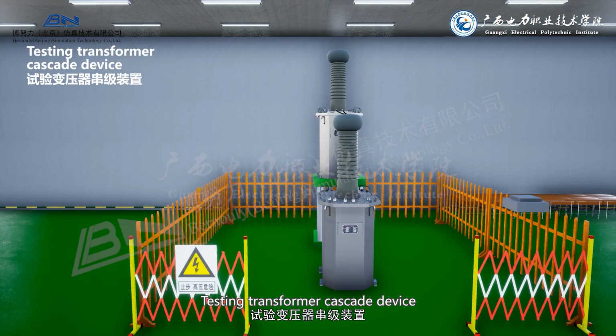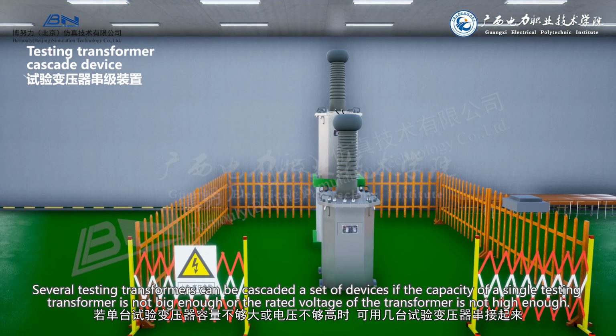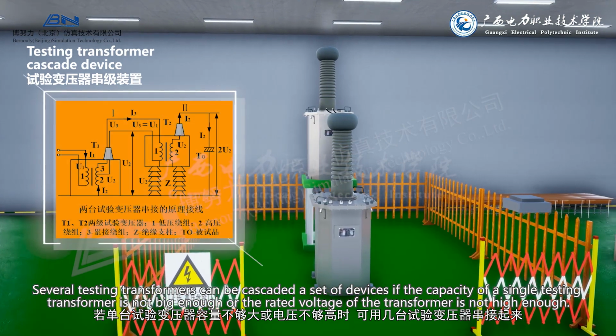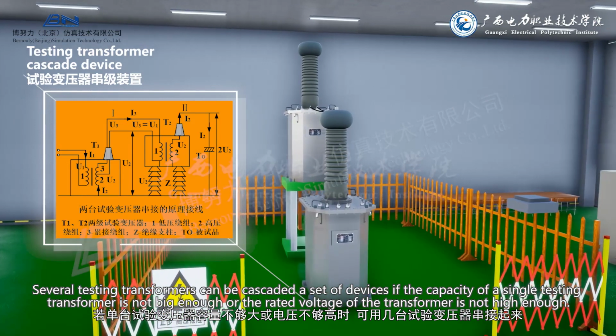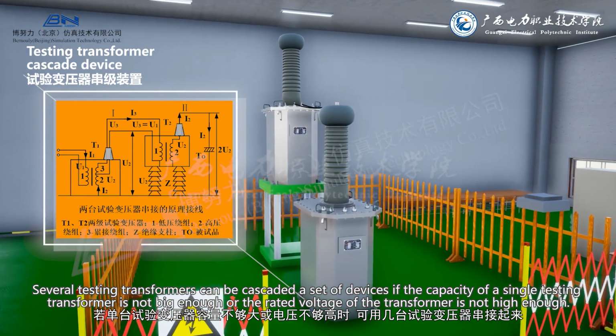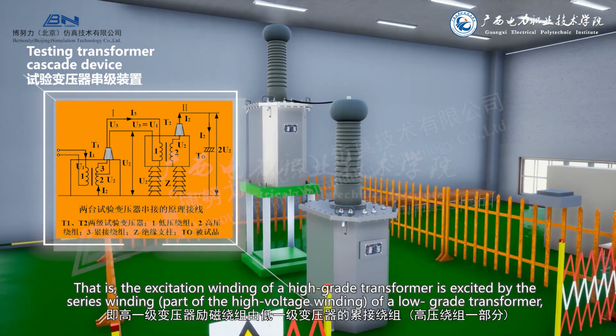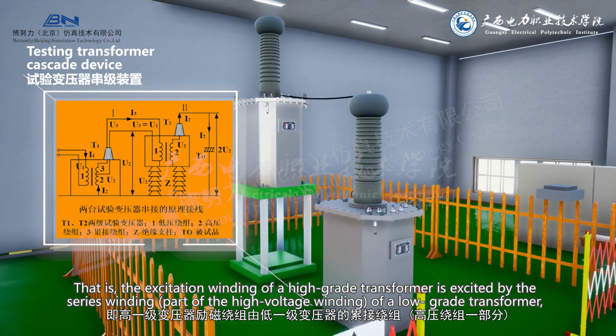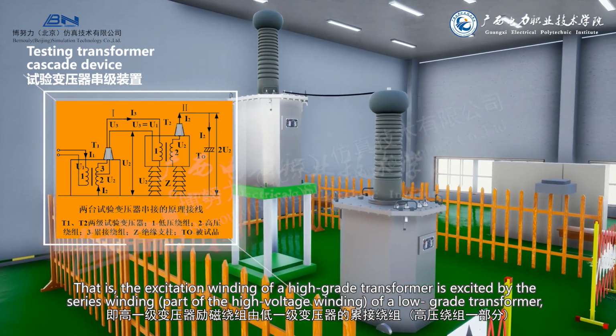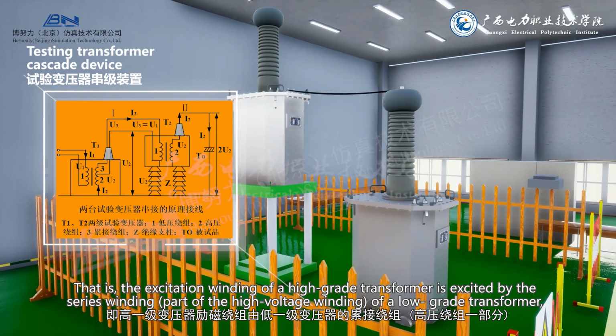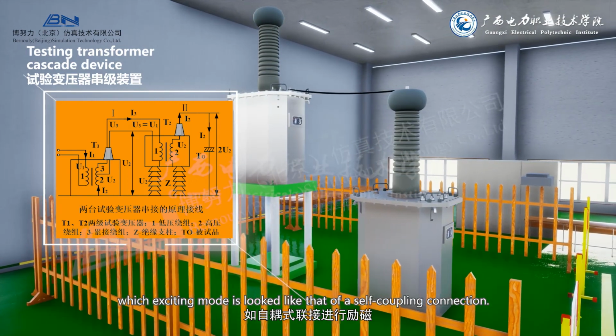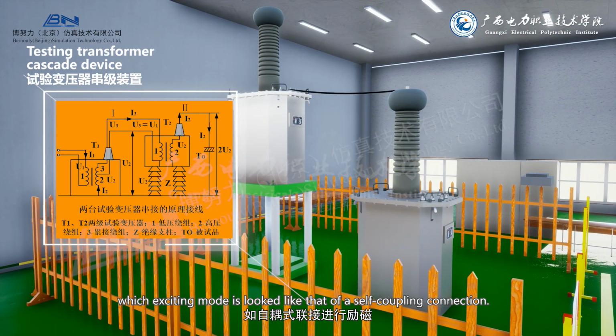Testing transformer cascade device: several testing transformers can be cascaded into a set of devices if the capacity of a single testing transformer is not big enough or the rated voltage of the transformer is not high enough. That is, the excitation winding of a high-grade transformer is excited by the series winding, part of the high-voltage winding, of a low-grade transformer, and this exciting mode is like that of a self-coupling connection.